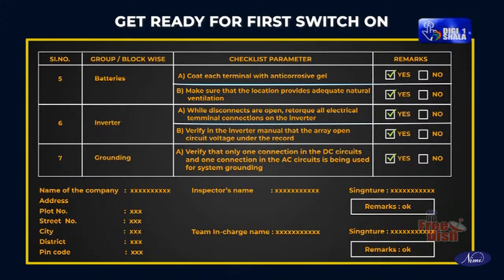Inverter. Checklist parameter. While disconnects are open, retorque all electrical terminal connections on the inverter. Remarks. Yes. Verify in the inverter manual that the array open circuit voltage is under the rated limit. Remarks. Yes. Group or blockwise. Grounding. Checklist parameter. Verify that only one connection in the DC circuits and one connection in the AC circuits is being used for system grounding.